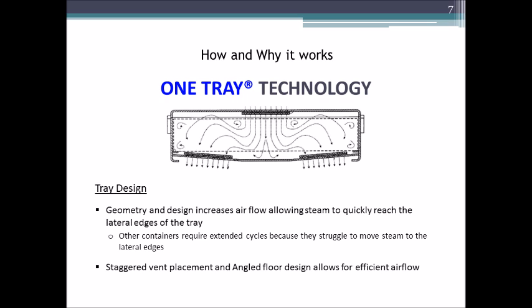The other containers on the market require extended cycles because they struggle to move steam through the edges of the container, whereas this system gets very good airflow. The staggered venting allows for an angled floor, and the angled floor allows for more efficient flow, giving you a greater volume of air movement through the container.